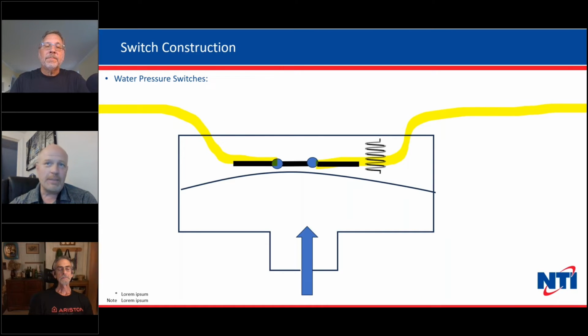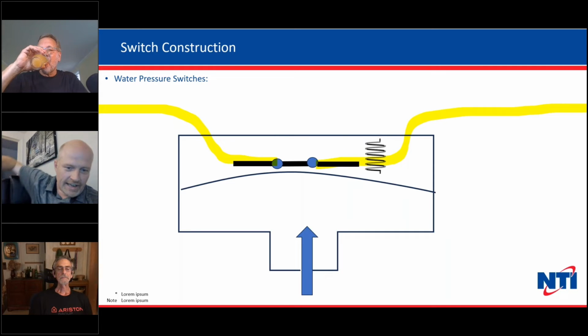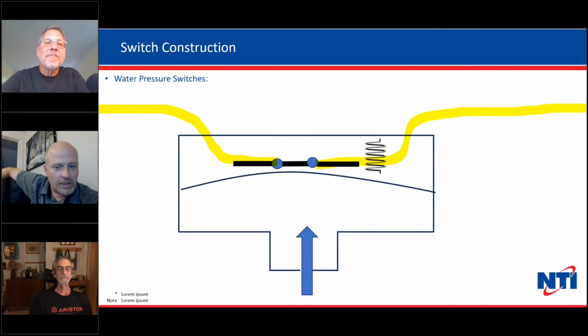Now these are adjustable, but because I'm not the best artist in the world, I didn't draw the adjustment screw, but you can imagine an adjustment screw tensioning that spring at the top. Those are factory set. They're not intended to be played with in the field. Oftentimes that switch is epoxy closed when you get it, but they actually do have an adjustment on them as well. That's what happens when you get enough water pressure, it will trip the switch. You can actually fake these switches into tripping. If you take a small rod and push it up inside the switch, you can activate the switch as well. They're just a physical rubber diaphragm. The contact gets closed by the diaphragm deforming and compressing the spring, and then it allows electricity to pass through.